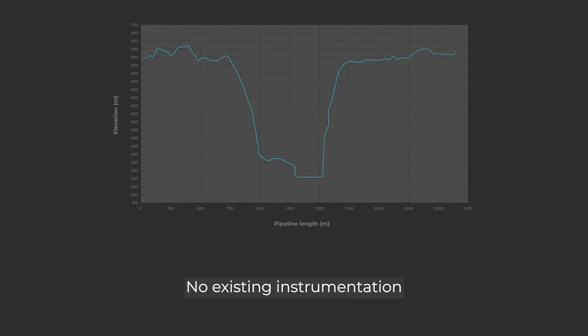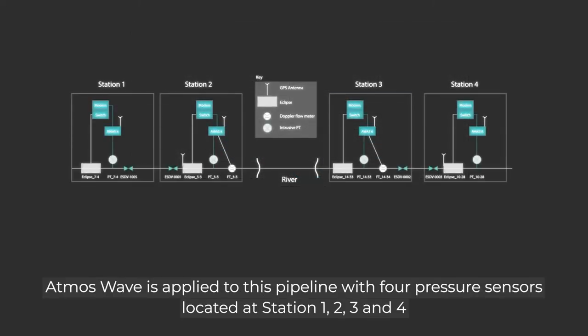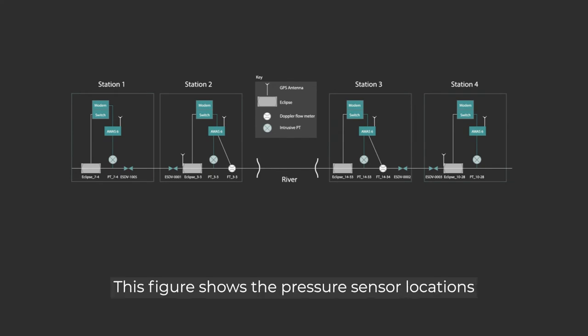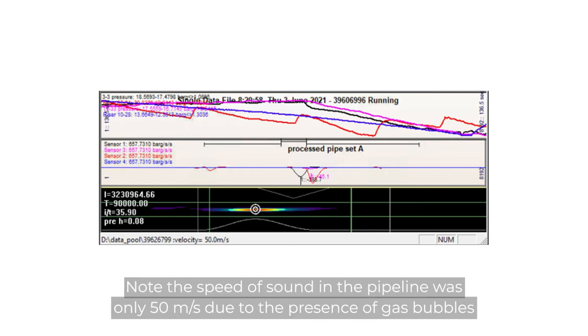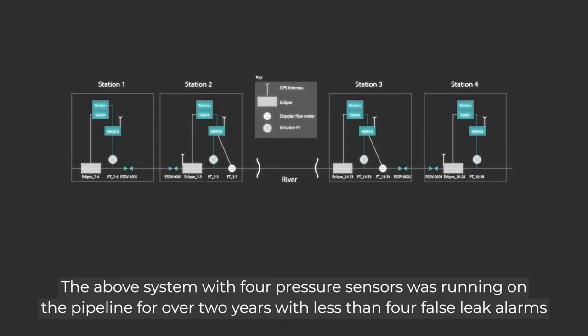Atmos Wave is applied to this pipeline with four pressure sensors located at stations 1, 2, 3, and 4. This figure shows the pressure sensor locations. This figure shows an example of one of the leaks being detected and located. Note the speed of sound in the pipeline was only 50 meters per second due to the presence of gas bubbles.